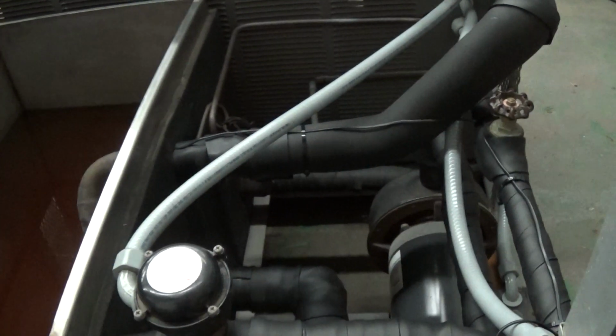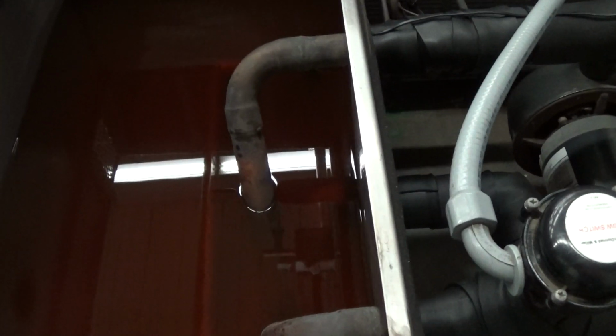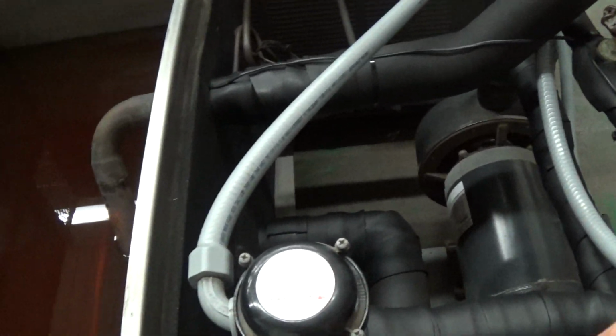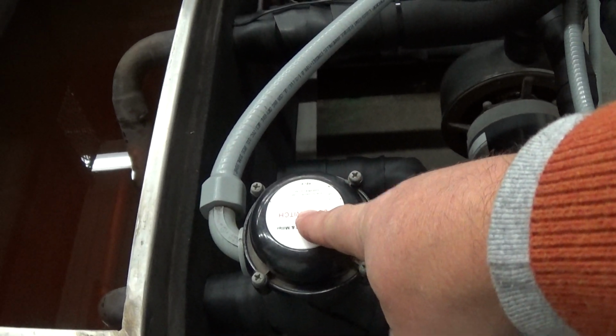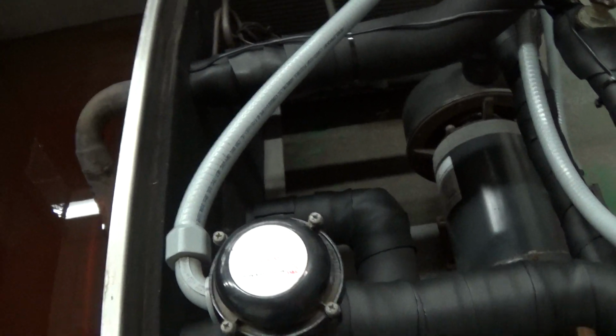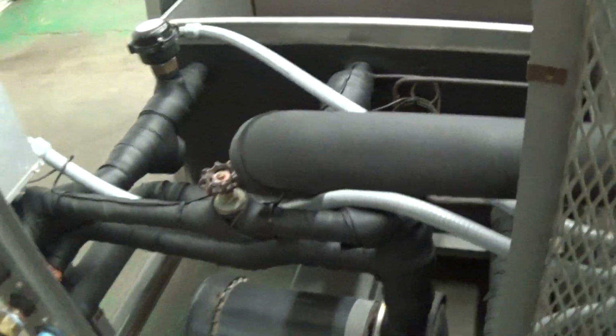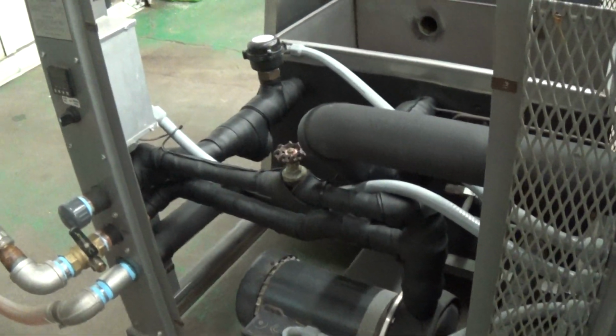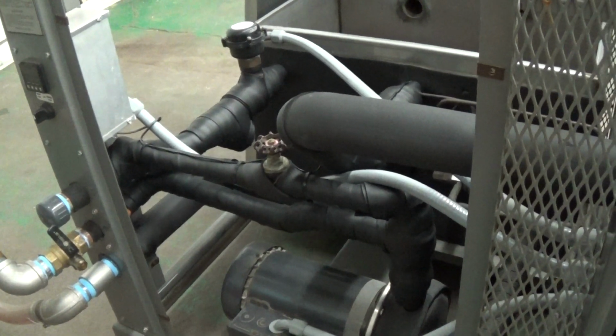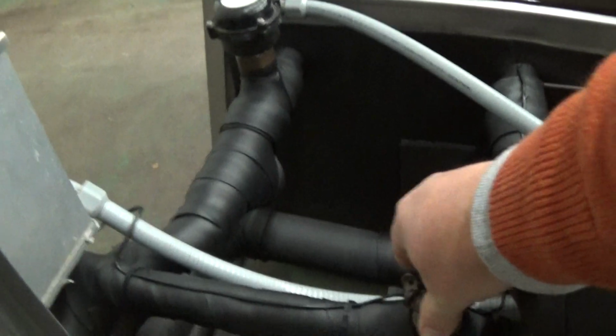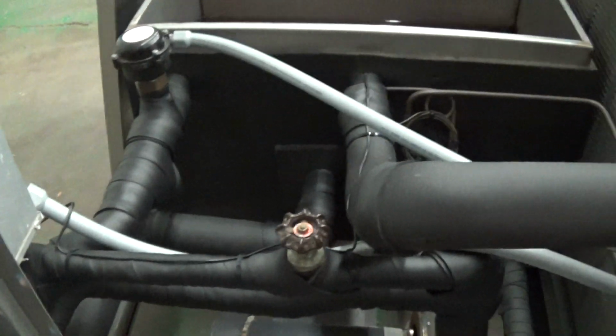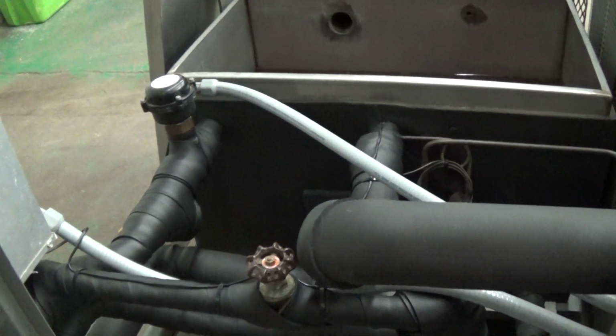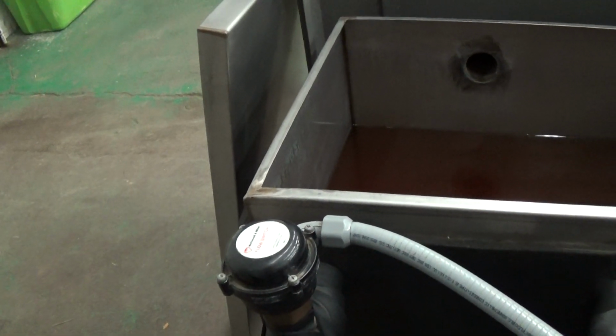So what that does is that ensures a heat exchanger, a brazed plate heat exchanger, consumes a certain amount of pressure. So this ensures that we always have that component of the equation satisfied, and we know we're getting enough flow to go back to the exchanger because of this flow switch. The other portion of the flow goes out to the process tanks. So in this situation here, you're not going to have to have your own bypass valve where your supply meets your return on your process tanks. So we have a globe valve here which adjusts the amount of flow going back to the heat exchanger in the chiller. If it's not enough, that flow switch will trip it out.